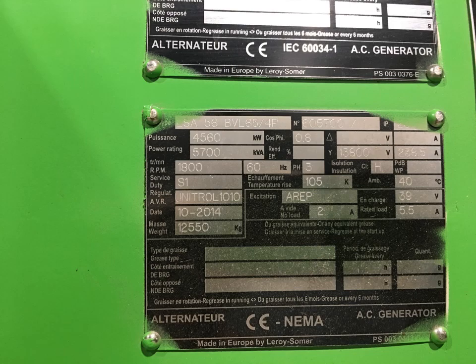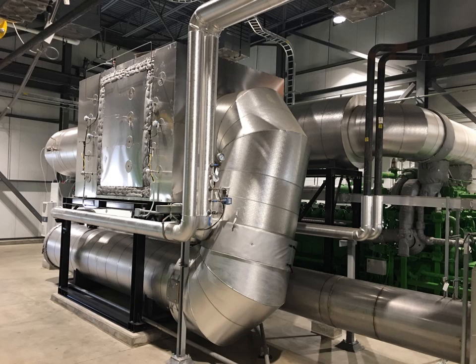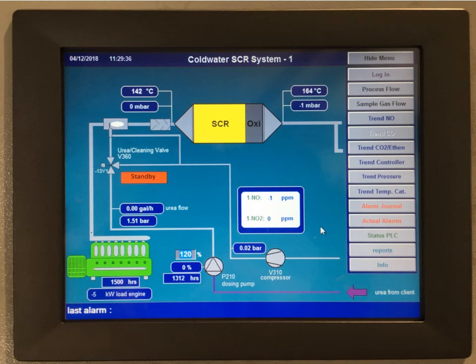This is a grid-connected AC synchronous generator. Here's a close-up look at the controls on the scrubber. This is an optional add-on: after condensing the water out, you can put the exhaust through a scrubber — a selective catalytic system — to eliminate NOx, unburned hydrocarbons, NO2, and ethylene, which is important because ethylene is harmful to tomatoes. The controller uses a catalytic converter and an SCR that injects urea — very similar to the DEF system on a clean diesel vehicle, just on a much larger scale. It gets the exhaust extremely clean, down to negligible NOx.